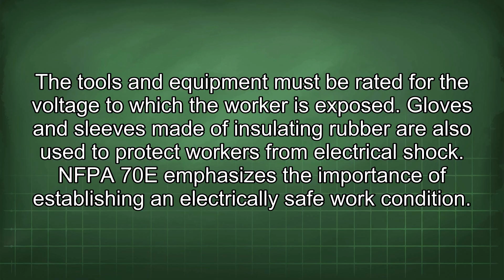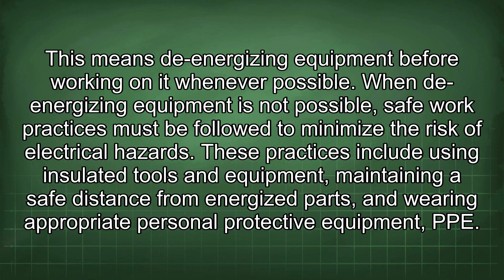NFPA 70E emphasizes the importance of establishing an electrically safe work condition. This means de-energizing equipment before working on it whenever possible. When de-energizing equipment is not possible, safe work practices must be followed to minimize the risk of electrical hazards.